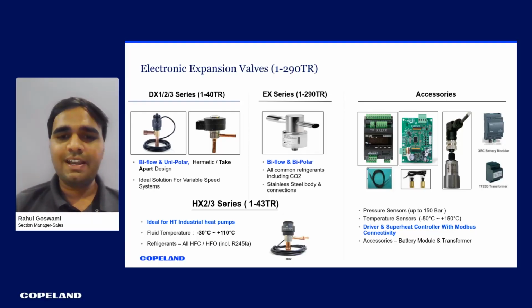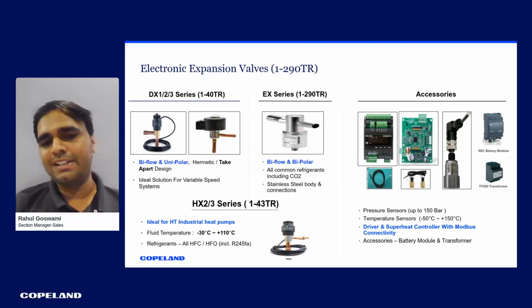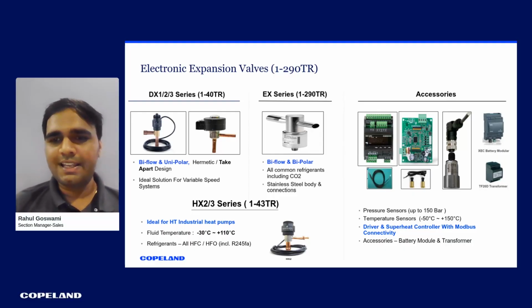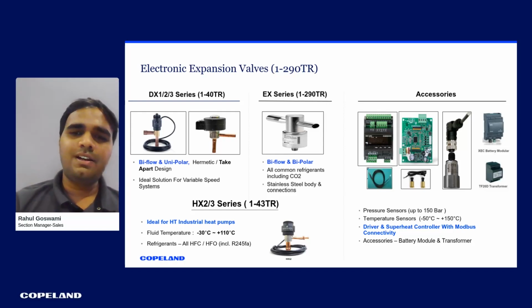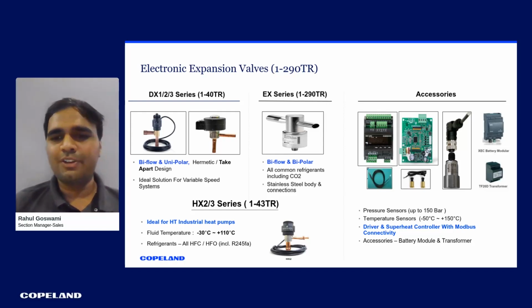And then we have HX series, which is up to 43 TR. It is very ideal for your heat pump applications. Basically, it can cover fluid temperatures ranging from -30 till 110 degrees Celsius. And as I said, we have all the accessories which are required to control these electronic expansion valves, like controllers, pressure sensors, temperature sensors, and all the accessories like battery module and transformers. Next slide.